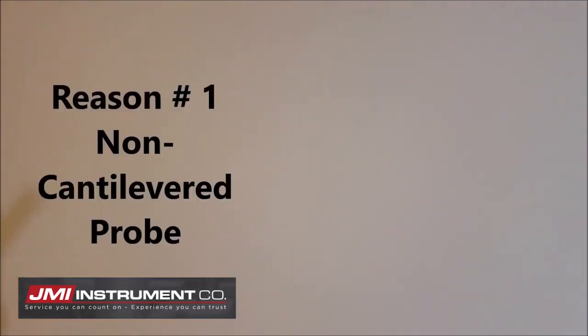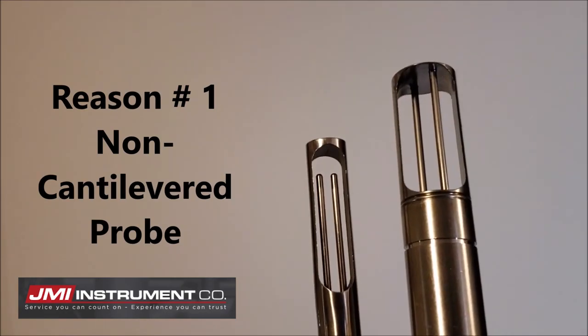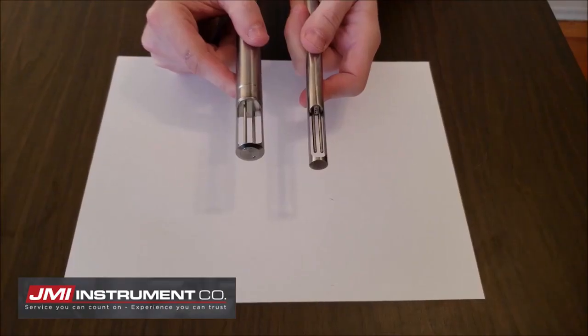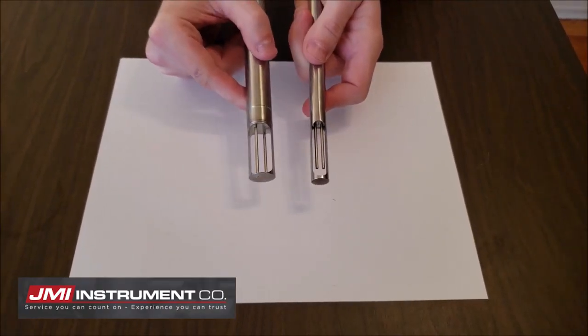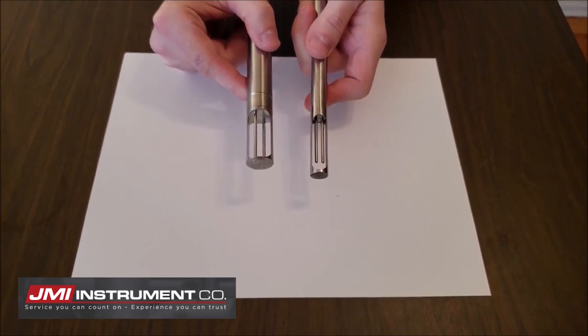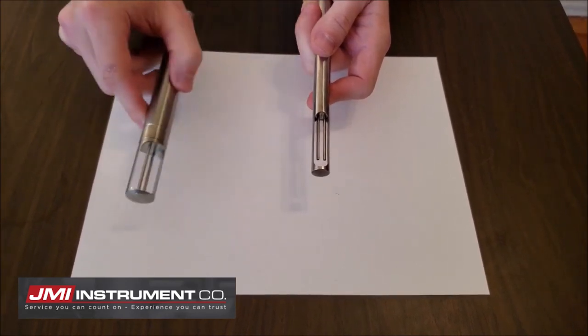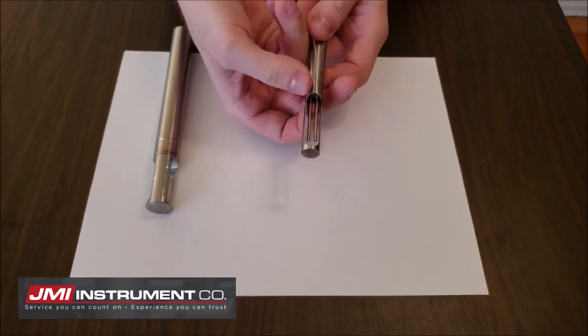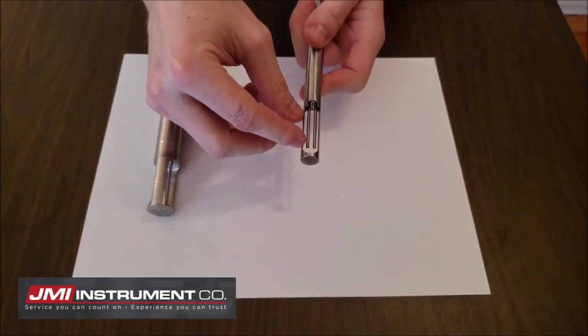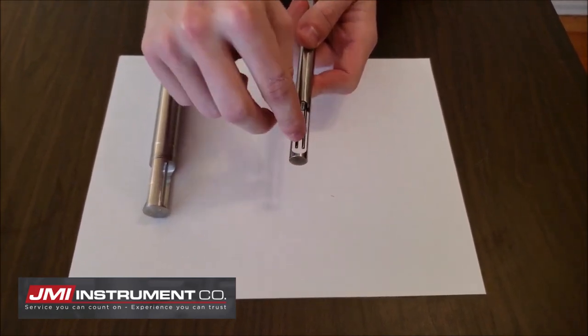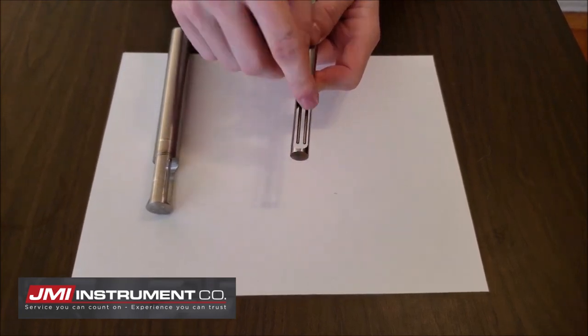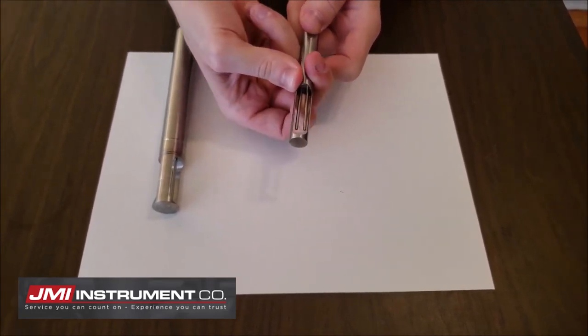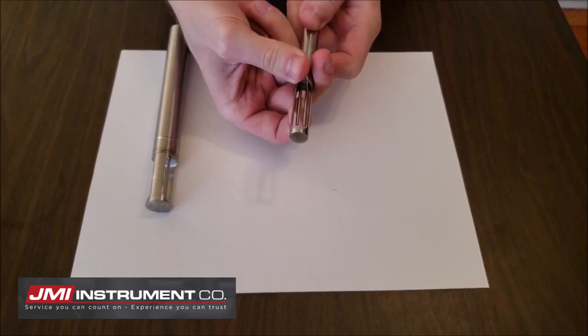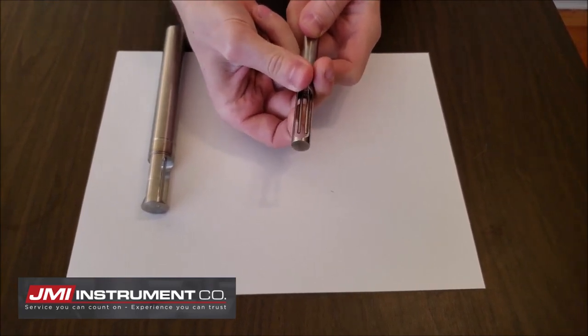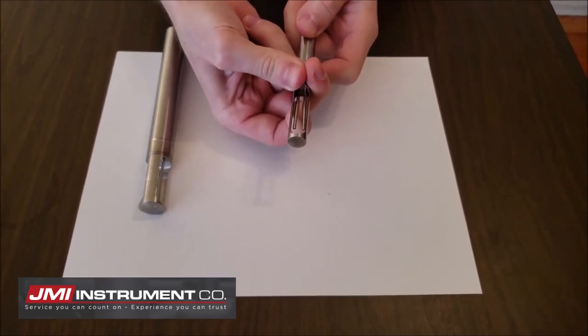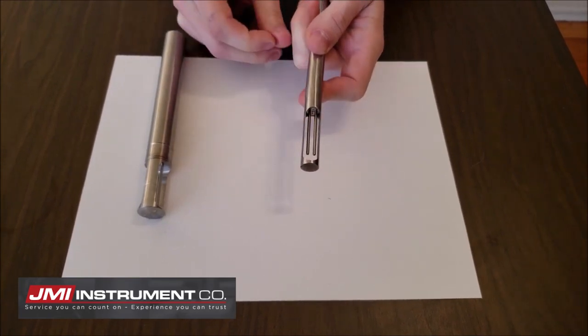Reason number 1, the non-cantilevered probe. All right, so the first question I have for you is, are you worried about your probes breaking off into the process? Most competitors to Fox Thermal, they cantilever their probes, leaving the non-attached tips of the sensors here. See how they're not attached to the head. They're vulnerable to vibration. You can see how I can move them even with my fingers. Damage from particulate, factors like that produce noise that unnecessarily lower the accuracy of your reading.